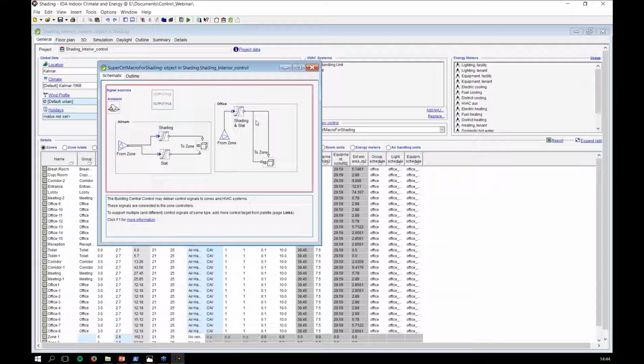In the links on the left-hand side, you'll be able to see signal sources and control targets. This basically gives you all the modules that you can get signals from and all the targets that you can send signals to. In this case, I'm using the zone sensor, this little guy here. What this zone sensor does is export all the signals from the zone to wherever I put this zone sensor. So here I'm connecting this zone sensor to the lobby.